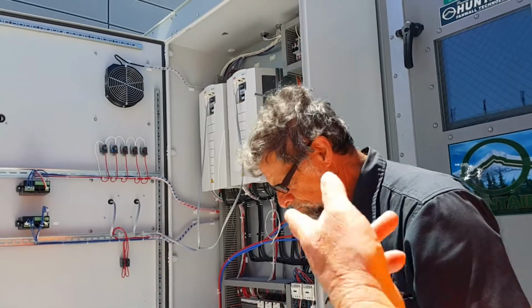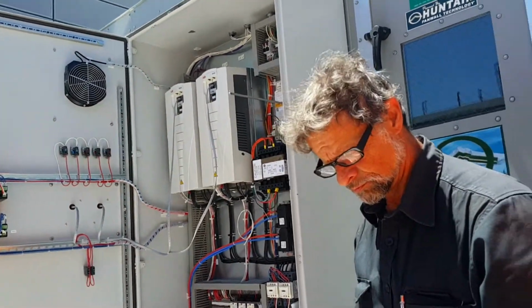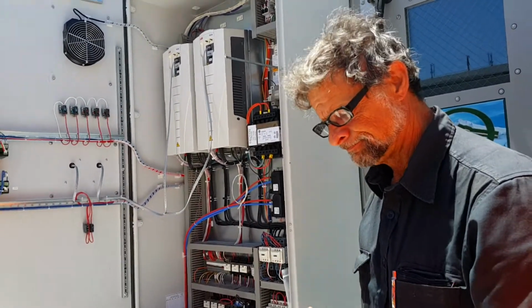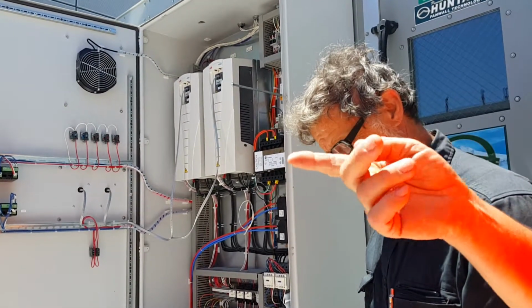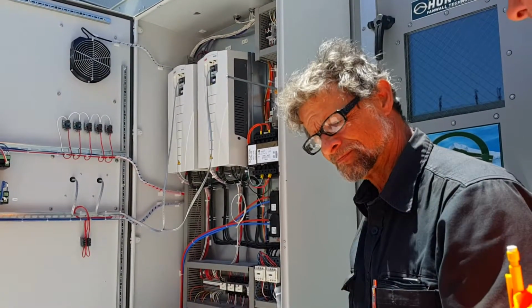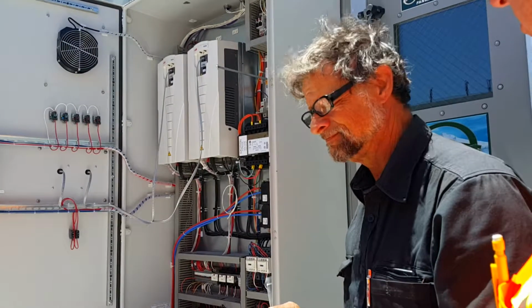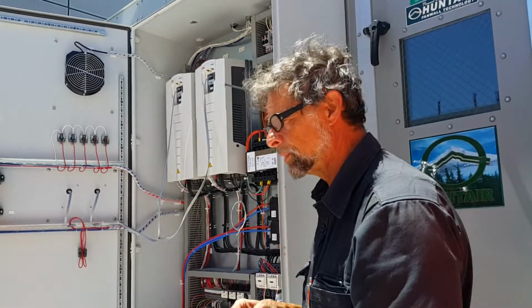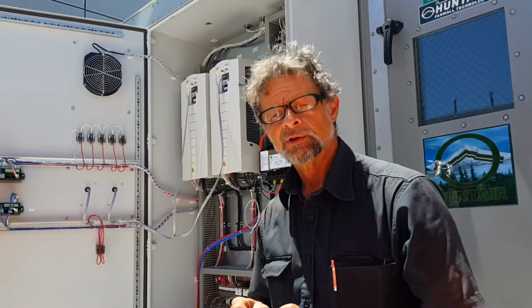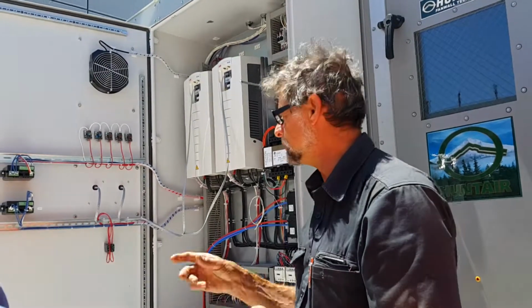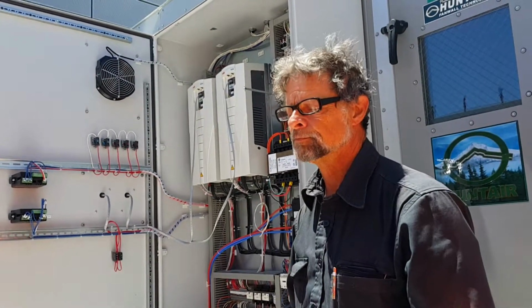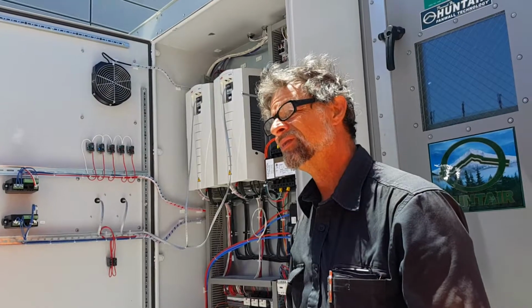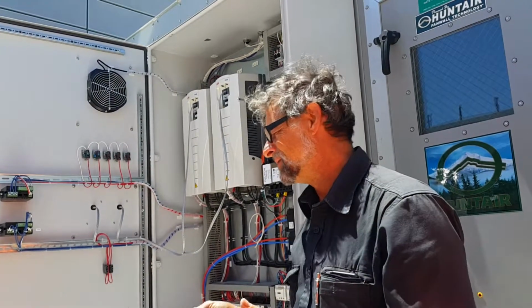The 2 drives on this unit, just because this unit is so important, has to keep running as a backup, right? And it doesn't transfer over to any of the other units, it just stays on H3. Yeah, my personal opinion is part of a maintenance program should be to switch them over. Part of our line starter maintenance.